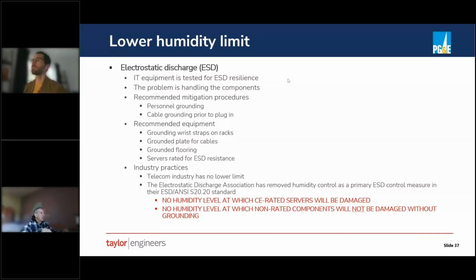A person can generate electrostatic discharge with your finger when you touch something, for example. And so if it gets too dry, the electrostatic discharge that a person can generate goes up. You can have more of a discharge. But the reality is that the IT equipment is tested for electrostatic discharge resilience and is generally immune from electrostatic discharge. The problem is when you're handling the equipment. If you open up the component of a server, then you're at risk regardless of the humidity level.